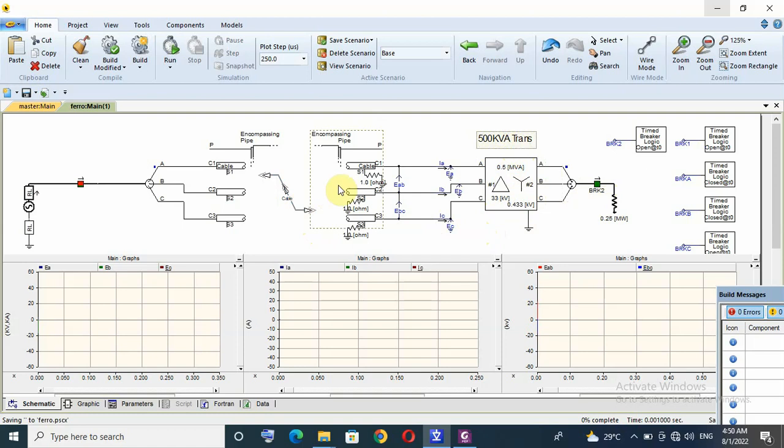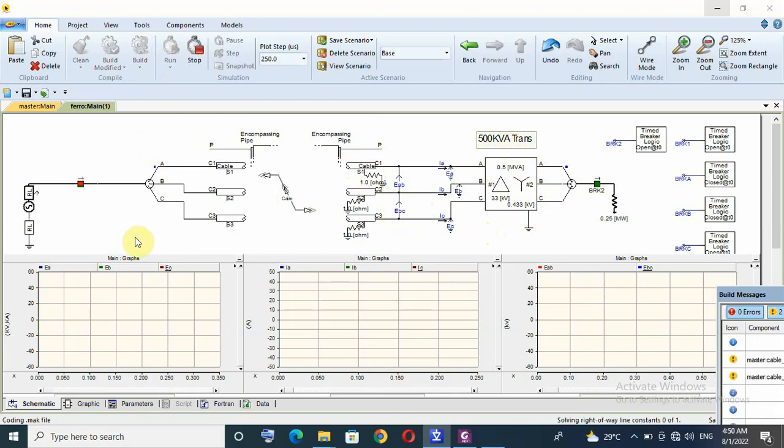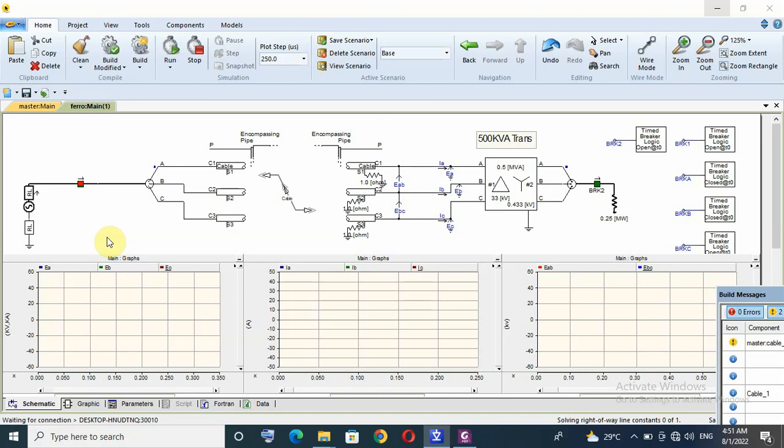And this cable is earthed at transformer side. So, let us run simulation and see if Ferro Resonance Phenomena happen or not in this configuration.